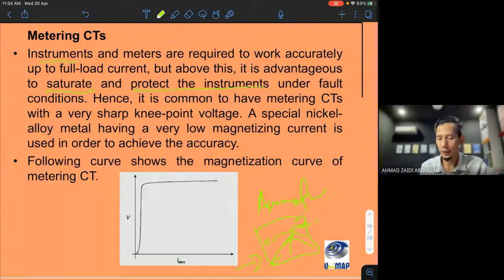If not, this CT that controls this. CT fault comes in, so maximum let's say 100 amp. So what will this CT submit? The current through the real instrument metering. So if the CT allowed the high current going through it to the meter, confirm this meter will be blown, the meter will burn. So that's the concept of metering.